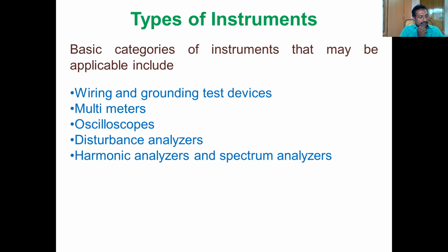Harmonic analyzers are advanced technology. Fourier transform calculations are also useful in this spectrum analyzer, which is also called the harmonic analyzer. But what are its capabilities? The capability to measure both voltage and current simultaneously, so that harmonic power flow information can be obtained using this harmonic analyzer.